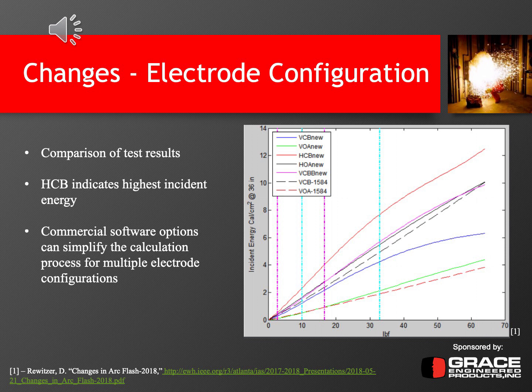Because each installation may have multiple types of electrode configurations in a single panel or a single enclosure, the question may become, which one is the worst case? If I don't do one, am I underestimating the incident energy? Or if I do one, am I overestimating the incident energy? Or we can actually have a much lower value, so that the person may not have to wear category 3 or 4 PPE, and maybe only category 1 or 2. So IEEE looked at it, and here's a plot of different configurations along with VCB and VOA, and a lot of the new values that were occurring.